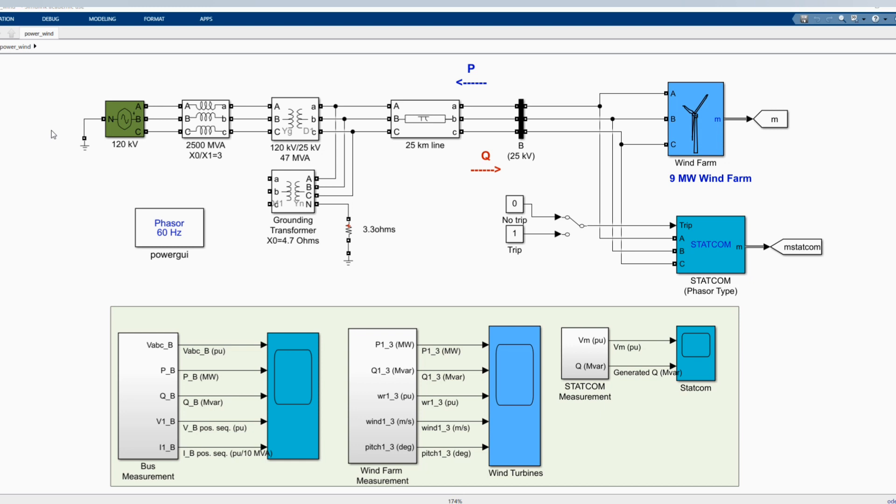Wind turbines use a squirrel cage induction generator. The stator winding is connected to a frequency of 60 hertz grid and the rotor is driven by a variable pitch wind turbine. The pitch angle is controlled in order to limit the generator output power at its nominal value for wind exceeding the nominal speed of 9 meters per second. In order to generate power, the induction generator speed must be slightly above the synchronous speed. Speed varies approximately between 1 per unit at no load and 1.005 per unit at full load.